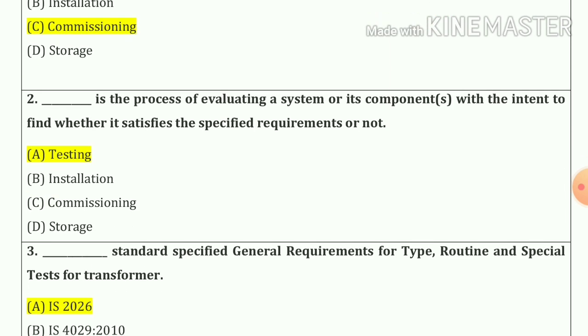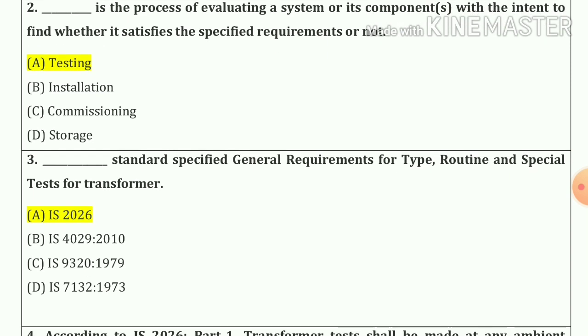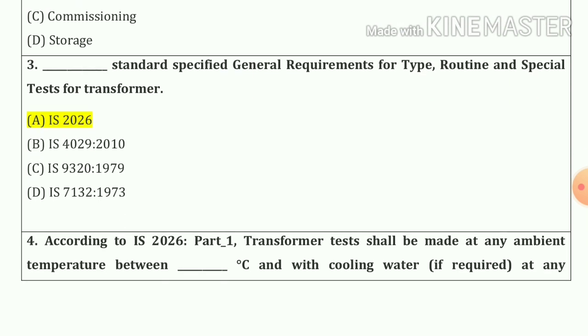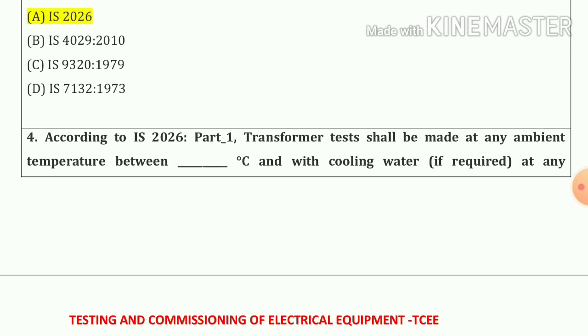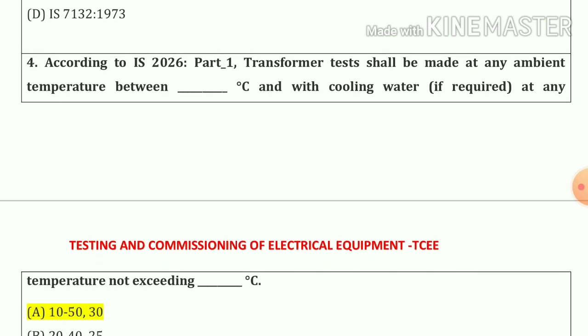Question number 2. Testing is the process of evaluating a system or its components with the intent to find whether it satisfies the specified requirement or not. Question number 3. IS 2026 standard specified general requirement for type, routine and special test for transformer. Question number 4. According to IS 2026 Part 1, transformer test shall be made at any ambient temperature between 10 to 50 degrees Celsius and with cooling water at any temperature not exceeding 30 degrees Celsius.